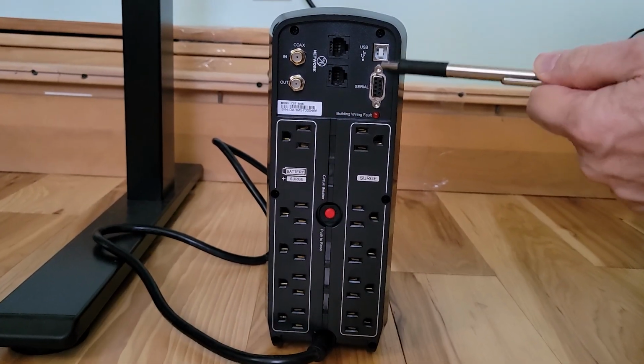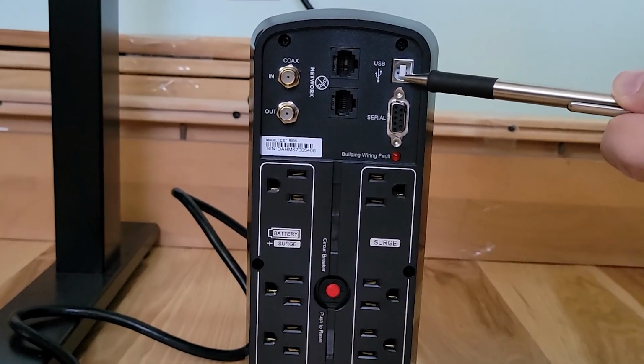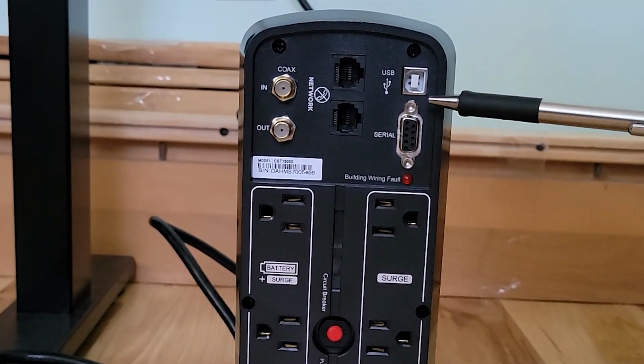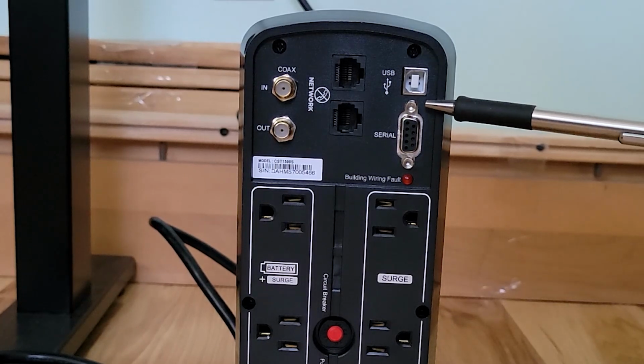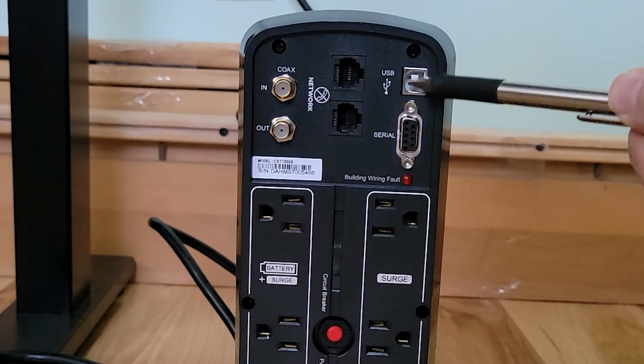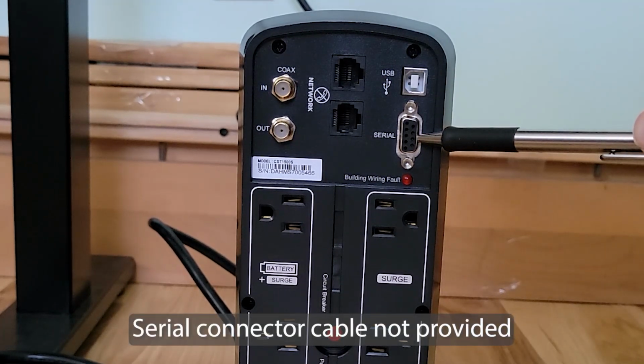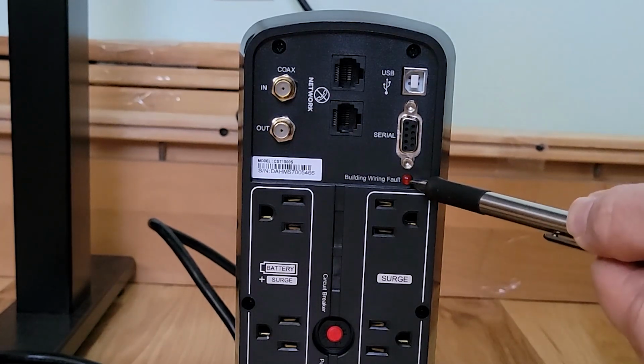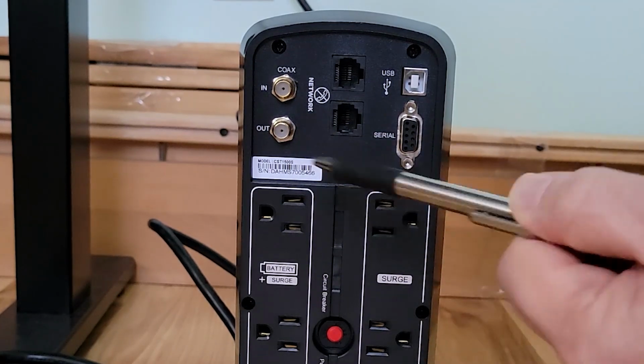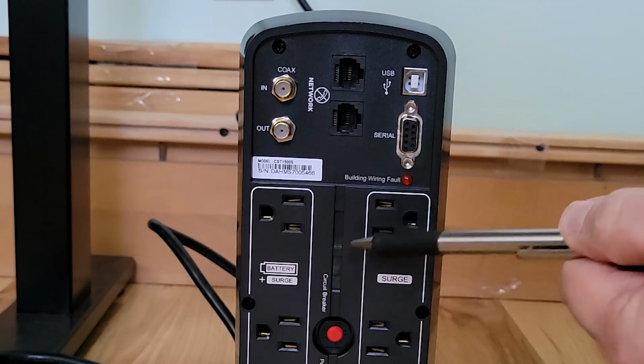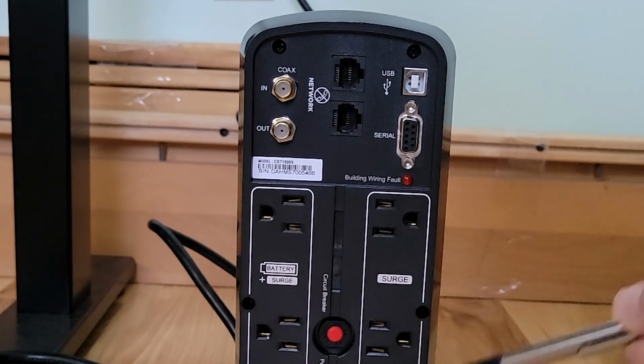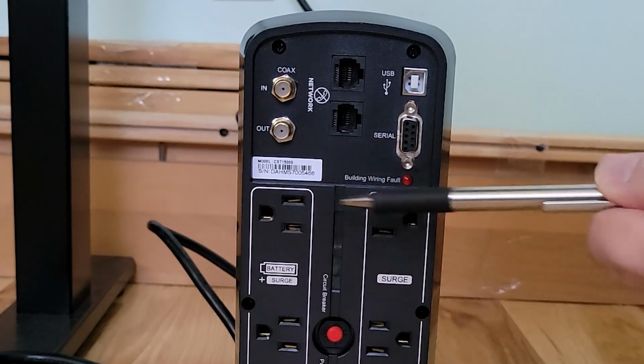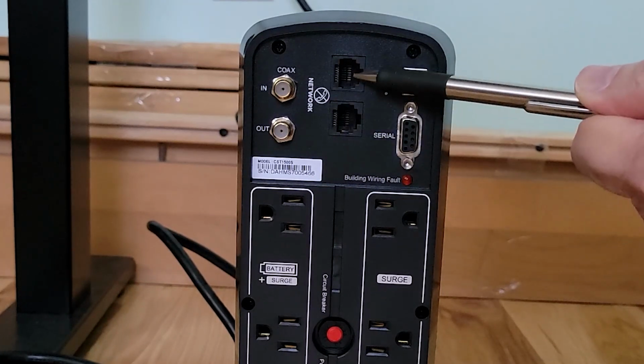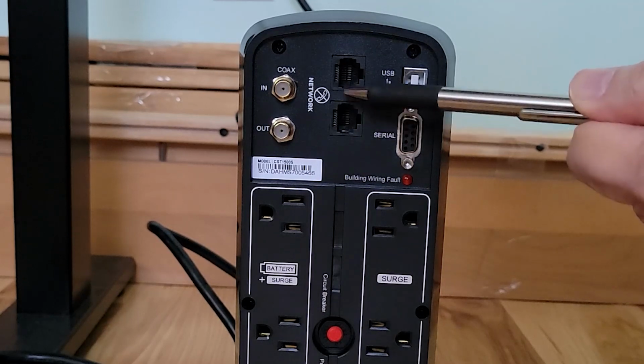Now let's take a look at the backside. Starting from the top right, we have a USB and serial connector. These allow you to plug into your computer so that you can control the internal operations of this unit via the software that you can download from their website. So you have an option. You can plug in with a USB cord that's provided or a serial connection cord to your computer. Below that, there's an LED light, and that will fault on whenever there's something that's wrong with the system. Cable's not grounded, the polarity is reversed, those types of faults will give you a red light. Basically what you do is you unplug everything, see if it clears the fault, and then slowly plug in one device at a time.